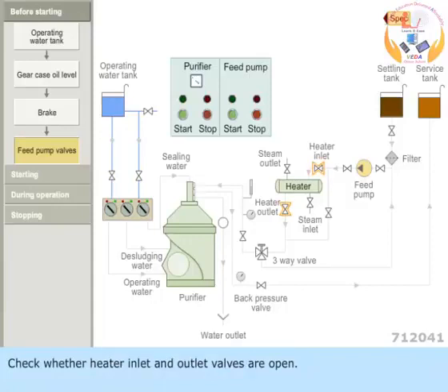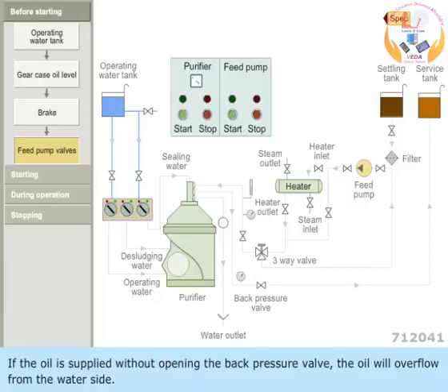Check whether the heater inlet and outlet valves are open. Open back pressure regulating valve at the outlet of the purifier. If the oil is supplied without opening the back pressure valve, the oil will overflow from the water side.